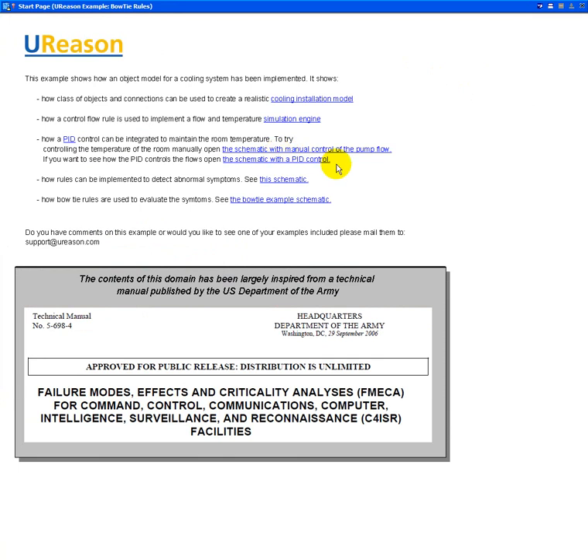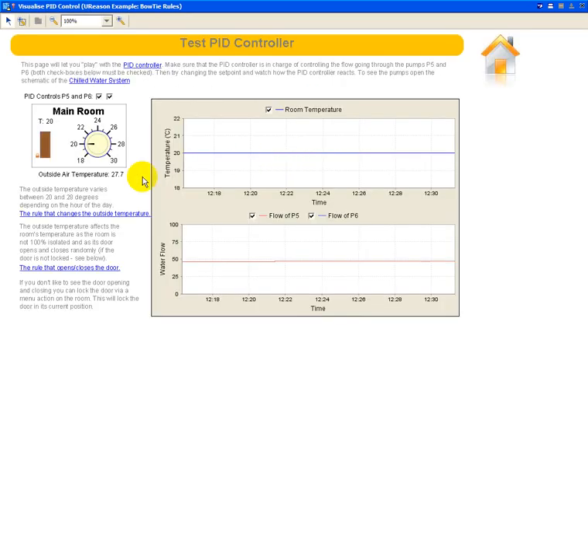Now let's have a look at the PID, the third entry of this demonstration, that shows how the temperature can be controlled inside the room either manually or with a PID control. Let's first look at the PID control. To show you that, I have here two graphs, one showing the temperature inside the room. It's quite stable for the last few minutes. It's been set to 20 degrees, so the PID is doing its job and making sure that the temperature inside the room is indeed 20 degrees. To get these 20 degrees there, the PID is actually asking both pumps, P5 and P6, to run at the same flow, at almost 50 here.